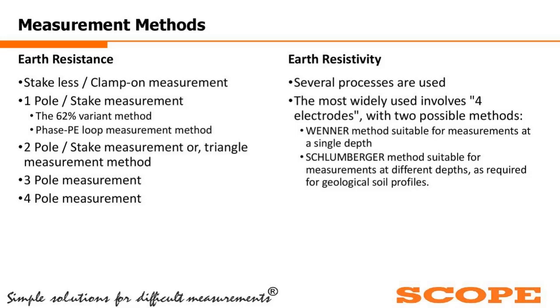Now coming to the different measurement methods for earth resistance and earth resistivity. There are various methods available. When it comes to earth resistance, people start with the most simple one, the stakeless or clamp-on measurement, where no earth spikes need to be inserted. You can use a clamp-on meter kind of earth tester, where you can get the direct value of the probable resistance. There are, once again, clamp-on measurement without signal injection and with signal injection. There are two types of clamp-on measurements available.